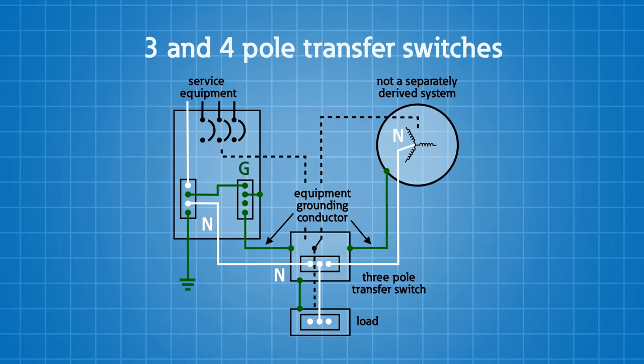Now, sometimes people will drive a ground rod and bond the generator hull or the structure to that ground rod, and that ground rod is supplemental. So it's not required by the National Electrical Code. It is a supplemental type of grounding. A purposeful connection between the neutral or that grounded conductor and that ground rod system, the grounding system over there on that generator, may occur in the field, either on purpose or by mistake. The important thing to understand is when you make that connection, you've established a separately derived system.